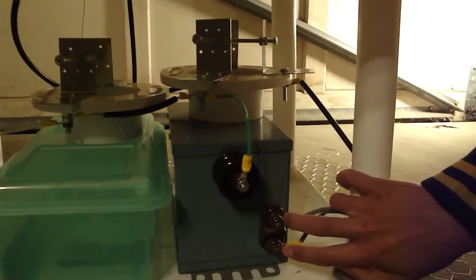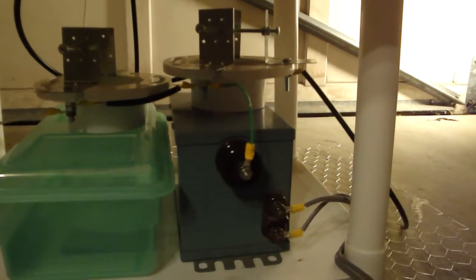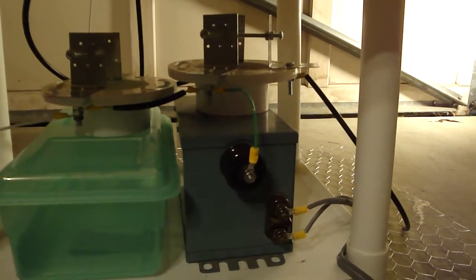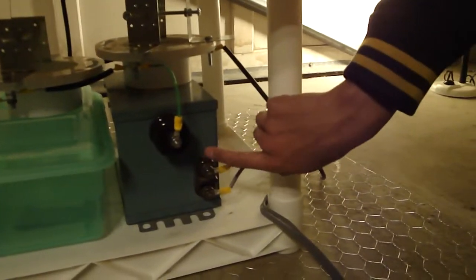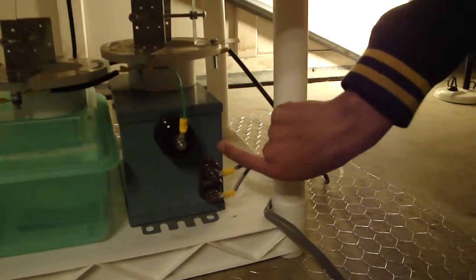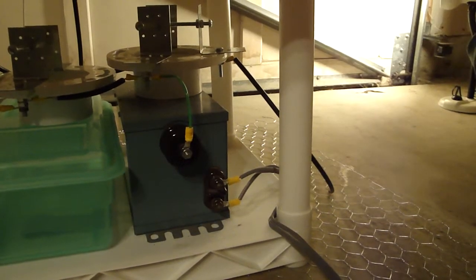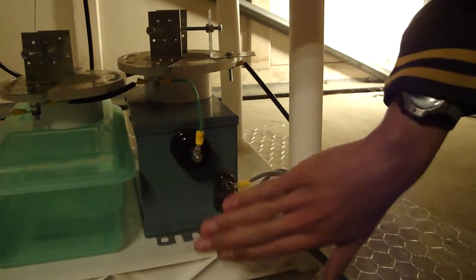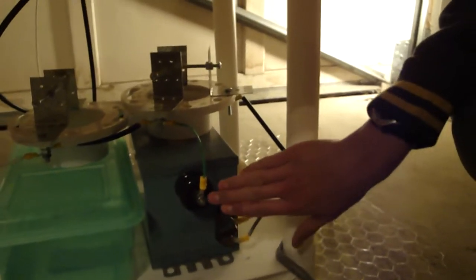Then, through the use of a primary coil and a secondary coil with a different number of windings, you can step up the voltage. So it sends it through a primary coil, and then through two separate secondary coils to get 6,000 volts between this electrode and the ground. And on the other side, you have another 6,000 volts between this electrode and the ground. But between them, there are 12,000 volts.